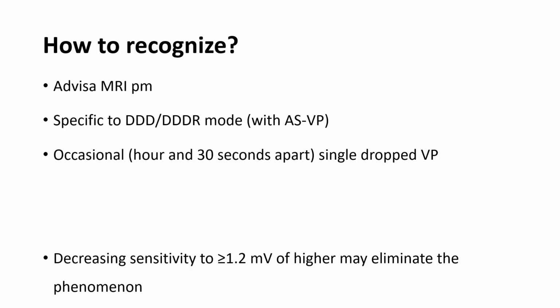And a solution that is being offered, and we're going to bring back the patient to our device clinic, and try to see if we can eliminate it, even though she's asymptomatic, is by decreasing the sensitivity. Now where sensitivity is 0.9, we decrease sensitivity to 1.2 millivolts or higher, and this may eliminate the phenomenon, as the noise will not be sensed. So I just want to go back to the patient just to prove that indeed this can explain the phenomenon we saw, the tracing we saw in this patient.